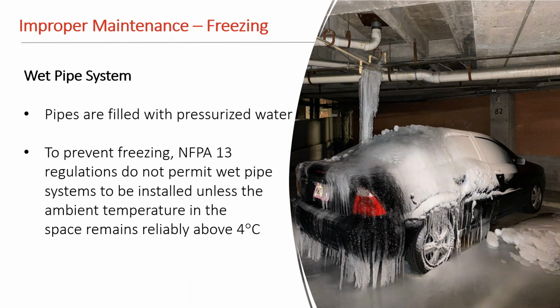Again, when it comes to maintenance, these systems are very reliable, but they do need maintenance. And it's good that the NFPA 25 guides and controls what kind of maintenance has to be done and must be done on the system. So the freezing, for instance, in a parking garage is something that shouldn't happen because those pipes should be filled with air. And yes, these are very interesting to investigate.